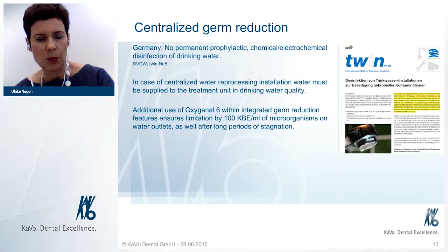So, and this is already the challenging topic. Of course, some centralized germ reduction device reprocessing installation could give you a result of drinking water, but you never can ensure that this drinking water quality really will reach the treatment unit itself. And therefore, of course, Oxygenal is highly recommended to use in combination either with a big water block, with this water block DVGW, or with the bottle system inside the treatment unit, to guarantee that in the thin treatment unit lines you have drinking water quality at the outlet of the spray or cooling water, whatever.